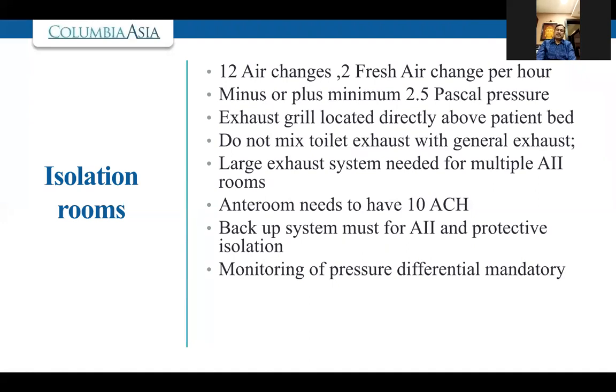Another requirement which has been added by NABH specifically is to monitor the pressure differential through a gauge. So you must have seen now that most of the hospitals are putting gauges for this, because it is pointless testing at one given point of time. So there needs to be a healthcare worker who is aware of these requirements rather than the engineers. Next, please.